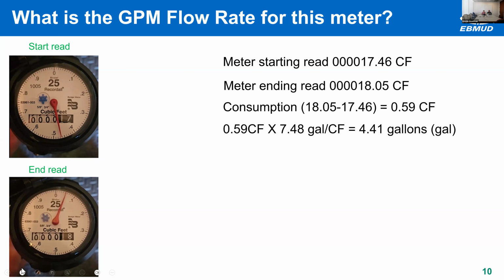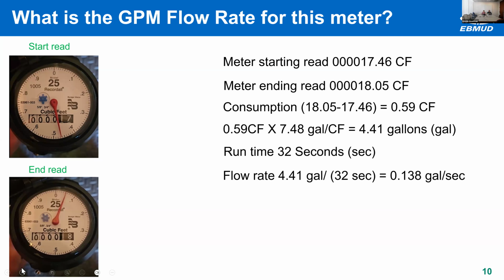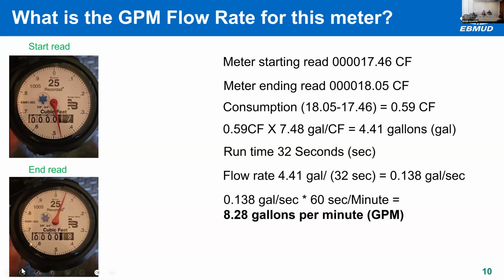And now we need to know the time between them. So we ran this meter for about 32 seconds. So we're going to take that 4.41 and divide it by 32 seconds. And that gives us a flow rate of 0.138 gallons per second. Now, we aren't measuring in seconds, we want to know minutes. So we would take this number and multiply it by 60 to get our gallons per minute, which brings us to 8.28 gallons per minute.